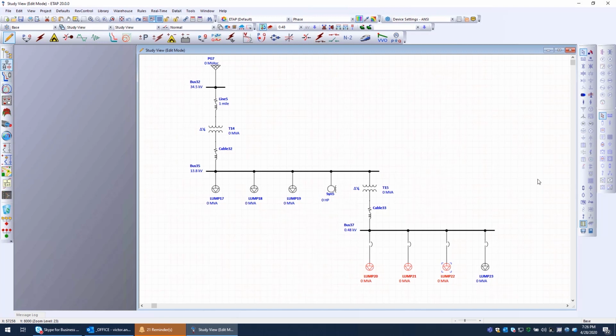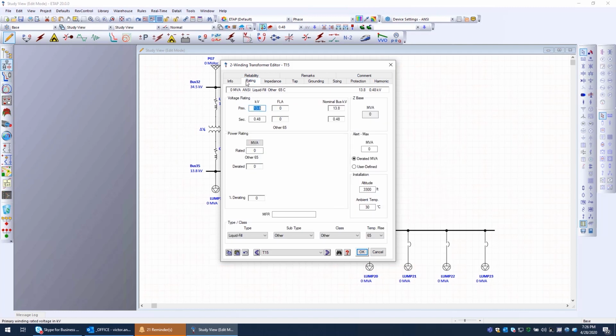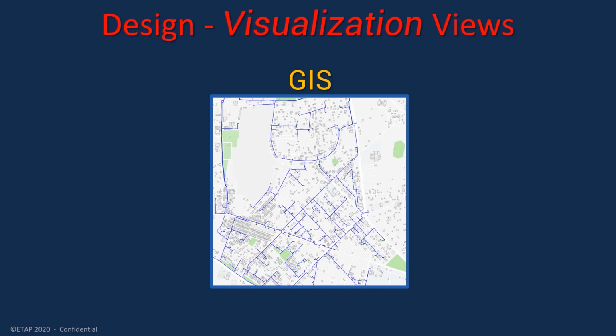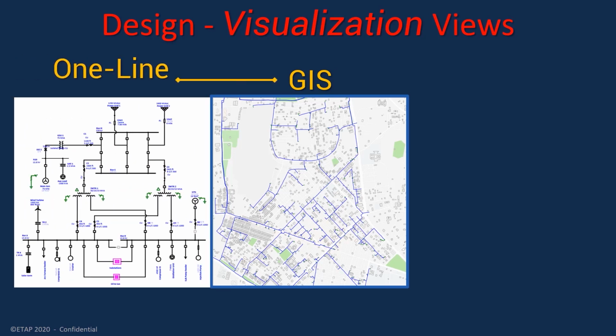After the connected single line diagram has been generated, the engineer would then double click on each element and enter the rating and the nameplate information as shown up on the screen. Now, for utilities and other sectors like railways, the engineer may choose to import the grid network data from an existing GIS database like Esri and generate an intelligent ETAP model with connectivity and all impedance information. This is necessary due to the vast number of circuits, loads, transformers, and other elements that may take months to generate if it was done individually by hand.